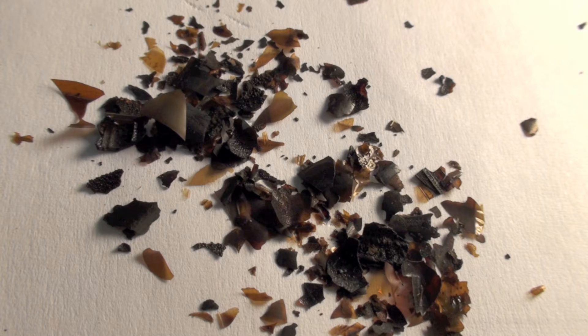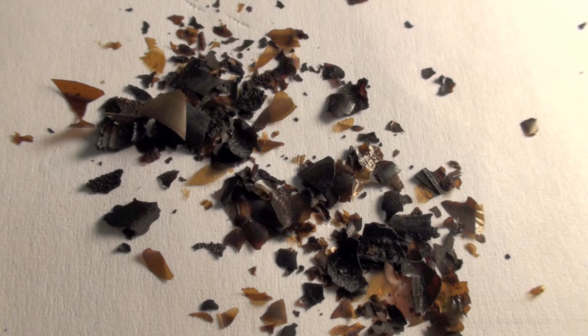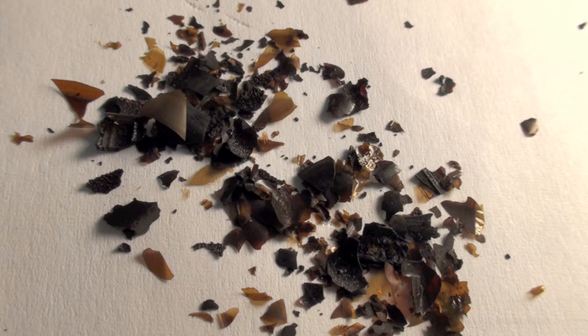The windings overheated and all these little bits broke off and were pumped throughout the system and were stopped by the dryer.